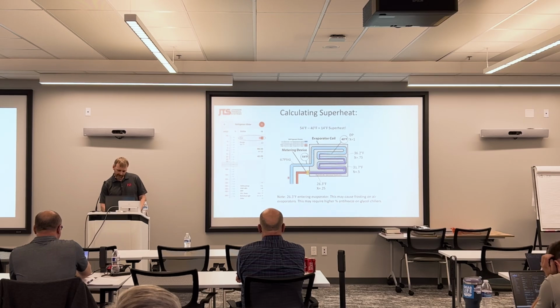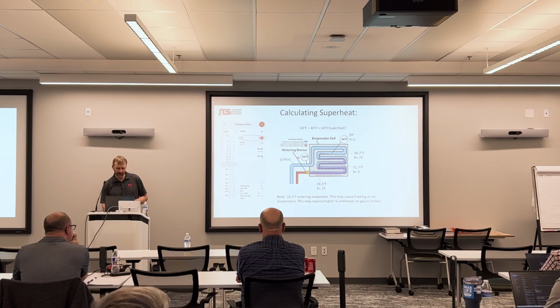So in this example here, we've got 67 psi measured on your suction outlet, and we've got 54 degrees at your pipe temperature. If we use our favorite converter tool or a gauge, you can convert 67 psi to approximately 40 degrees, and you can deduct 40 from 54 to calculate your 14 degree superheat.